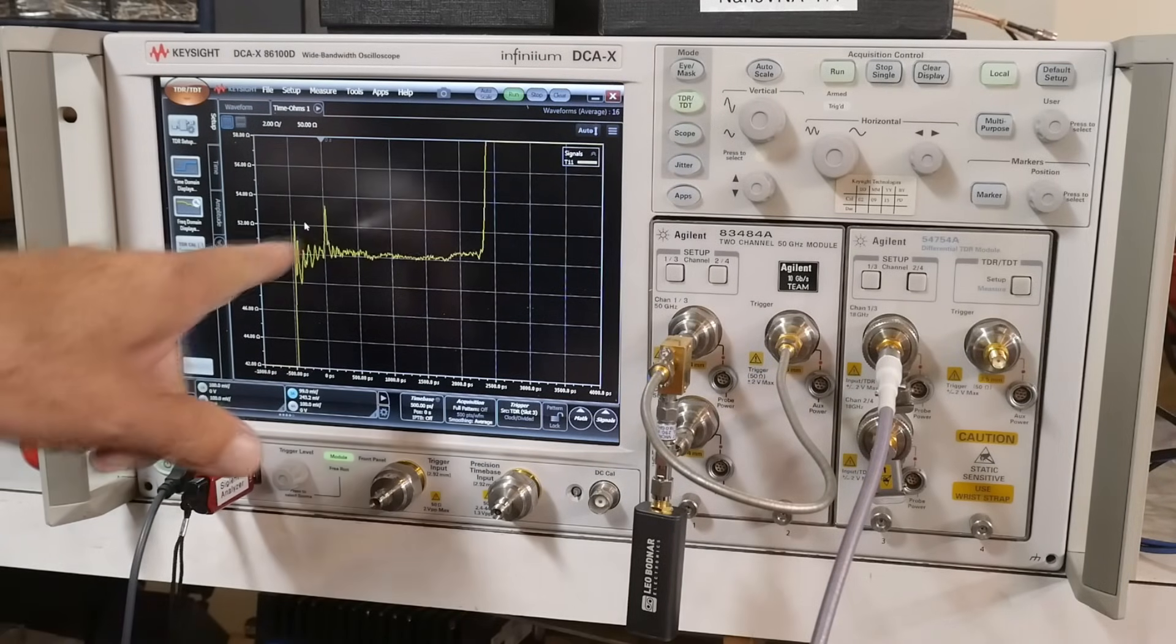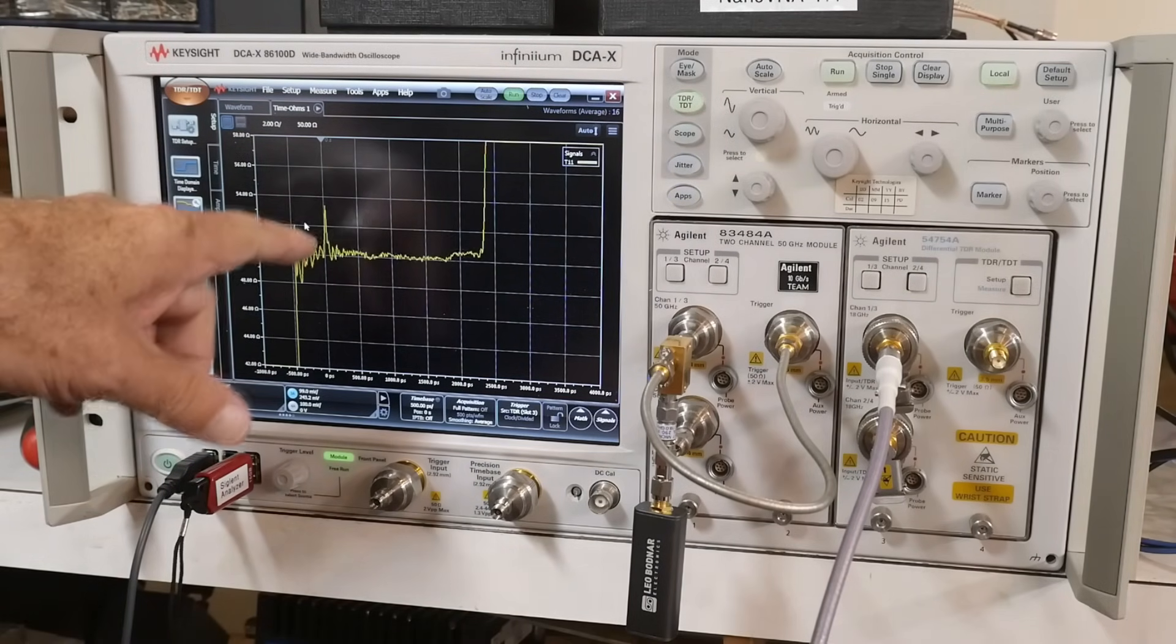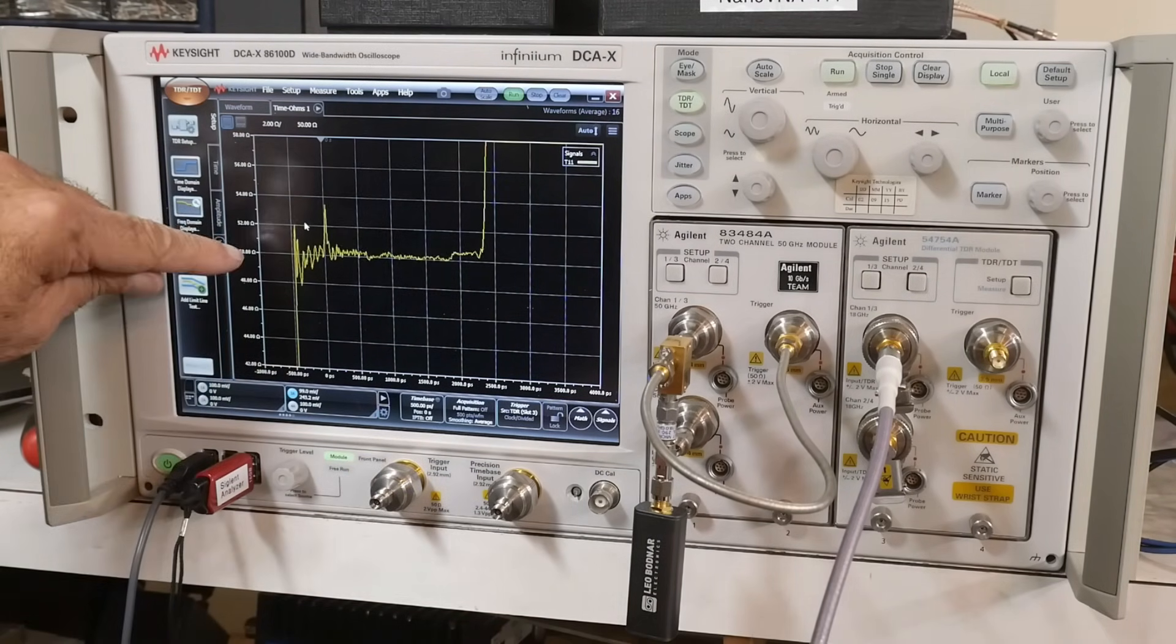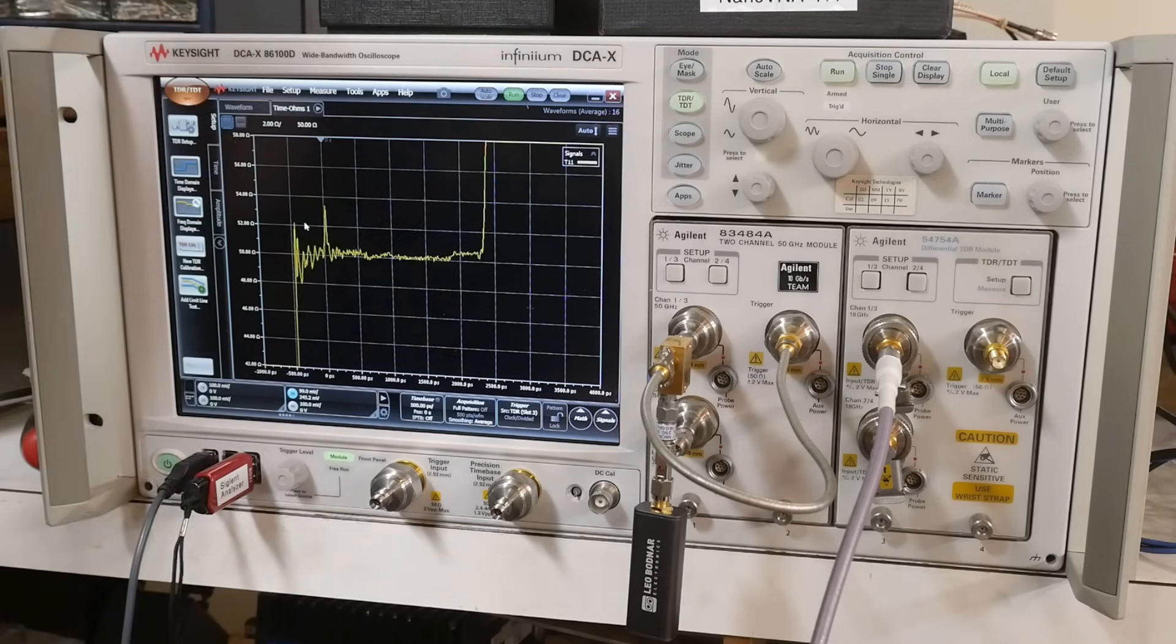Okay, so right away we see there's a spike right here. So we look like we're 50 ohms. This is 50 ohms, 52, 54, 55, 56 full scale. And that's because we haven't torqued it down yet.